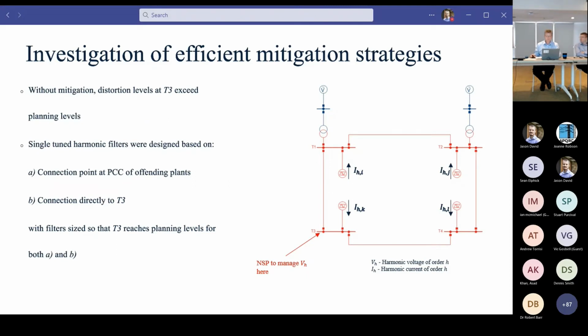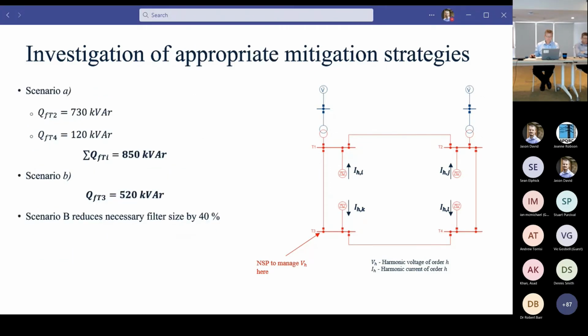First, we look at the filters that will be connected at the PCC of the offending plant, so at T2 and T4. And then we'll look at a scenario in which we connect the filter directly to the point at which the planning levels or the voltage distortion levels are the highest. If we compare the two, the size of the filter for the connection at T2 will need to be about 730 kVAR. The size of the filter for the connection at T4 is about 120 kVAR.